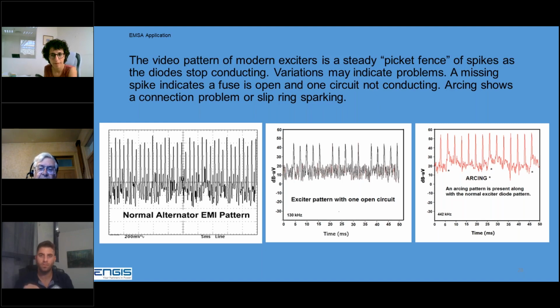It's a steady pattern. It does not change. The top of it may include a sine wave like this one does. It may be straight across. That depends on the design of that exciter. So each one is unique, but they don't change. If one of the spikes is missing, that diode circuit is open. And almost all of these are a full wave rectifier, so there are 6 spikes and then they repeat again. Here, one circuit is open. A diode has shorted and a fuse has opened up. If there's a wide spot down at the bottom, that shows arcing. So here, all of the diode circuits are working, but I've got arcing present.